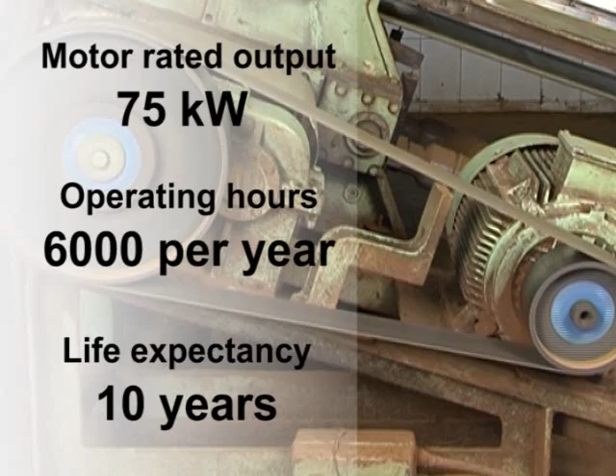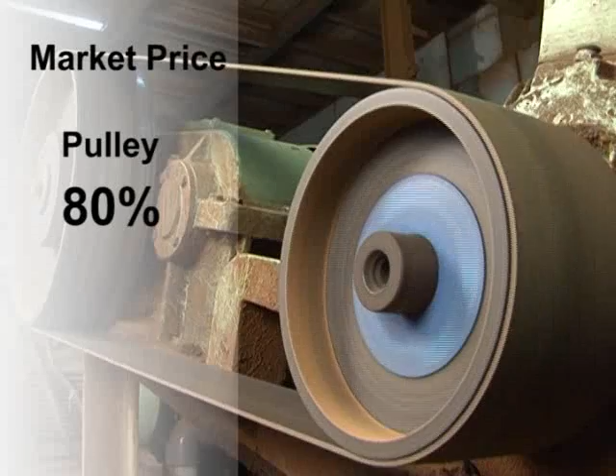In assessing which drive system is more economic in the long term, the following aspects have to be taken into account. For example, in the case of a belt drive, if a motor's rated output is 75 kilowatts, operating hours are 6,000 per year, and life expectancy is 10 years, then for initial outlays, the market price of pulleys is 80% and that of belts is 20% of the system price.